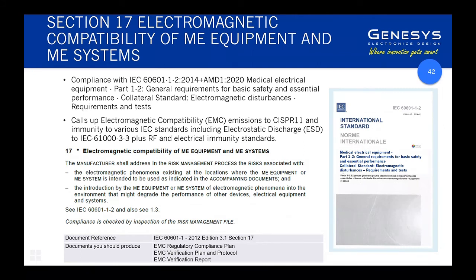Electromagnetic compatibility is called up by way of a collateral standard — 60601-1-2 — which specifically addresses EMC. This calls up CISPR 11 for emissions, along with a range of other requirements. Electrostatic discharge is one of the most critical. Immunity standards apply in Europe for commercial equipment as well as medical, but in Australia the susceptibility requirements do not apply for non-medical — they do apply for medical, so be aware of that difference.